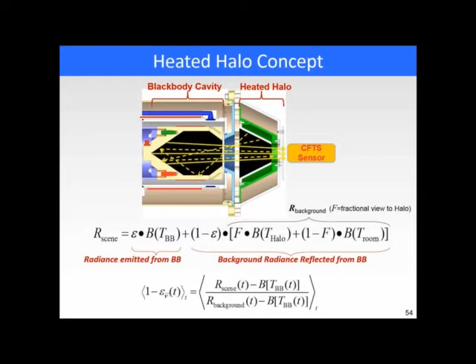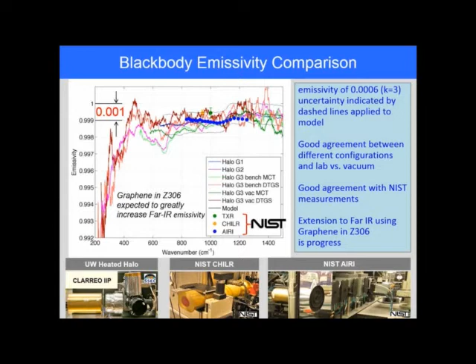And this would be the result that we would get. So spectral emissivity as measured by the calibrated FTS. And because we have always used the same geometry of black bodies, we have a big history working with NIST and different NIST facilities. And there's overlaid on here several different of those measurements. And everything has been very consistent with each other and with some modeling that we've done also. So the one thing I want to point out here now is this drops off significantly here, and we want to be out to 50 microns. We want to be having a much higher emissivity out there. It's really the limitation of the paint that we use, and I'll just describe later what we're doing about that.